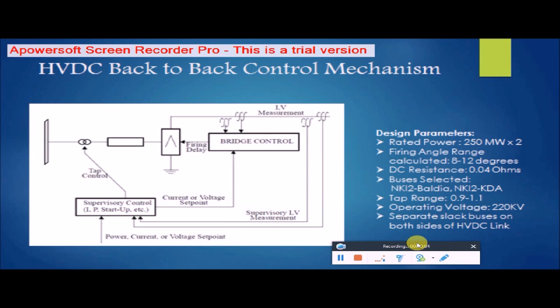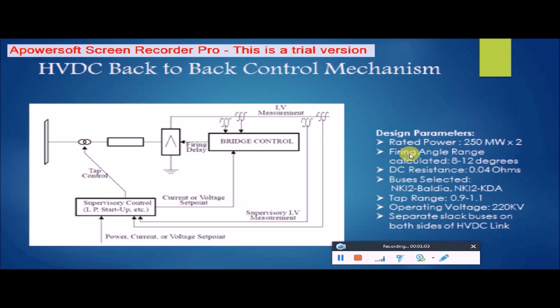Now we look at the incorporation of the HVDC back-to-back link in our project. The basic control mechanism has two types of controls. The first is firing angle control, where we control the amount of current flowing through the converter station by means of the firing angle delay — and by controlling the current, we effectively control the power flowing between the two utilities. The second is tap control, incorporated behind the rectifier and after the inverter. Together, the firing angle and tap control fix the maximum power at the specified limit.